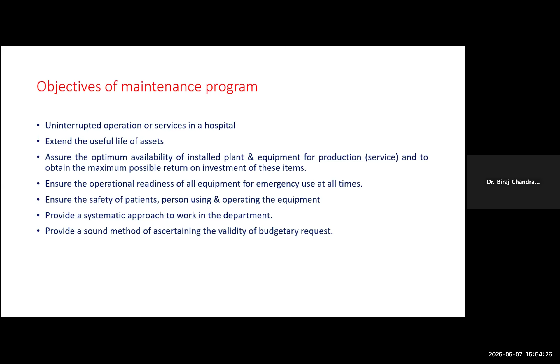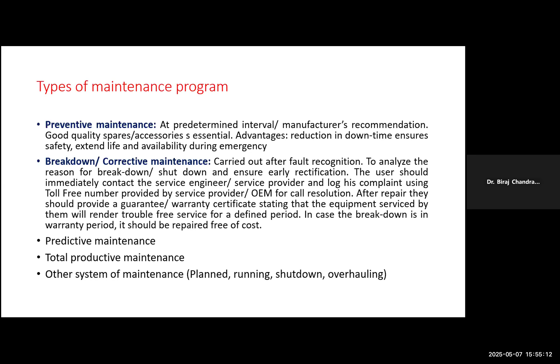What are the different types of maintenance of the equipment? One is preventive maintenance. Preventive maintenance is always done at a predetermined interval. So you must have software where you can check the intervals of all the medical devices of your institute. Then there is another system called breakdown maintenance, which is carried out after fault recognition. When there is any breakdown of the equipment, that is done. What is predictive maintenance? Predictive maintenance is based on the analysis of your data and predicting the maintenance time. And total productive maintenance is a holistic approach, right from the management to the operator, who all will be dealing with the maintenance process of the equipment.